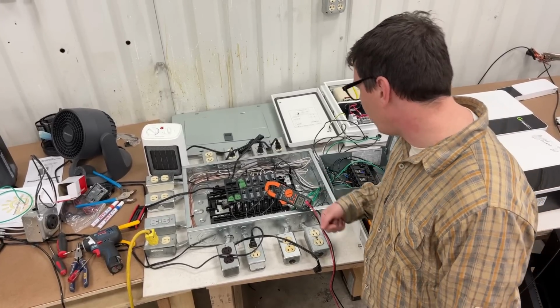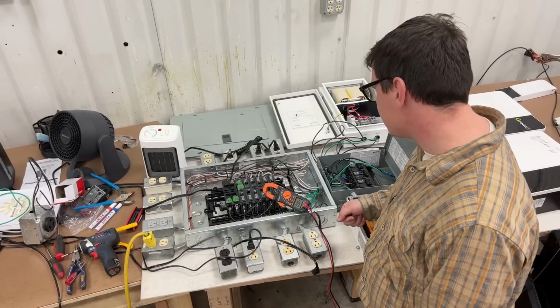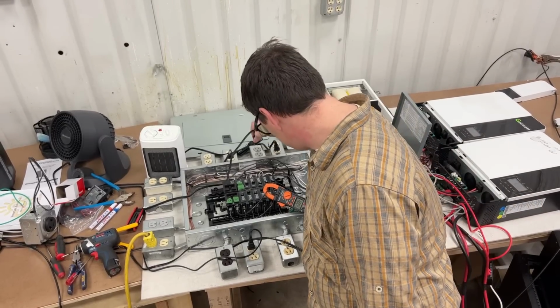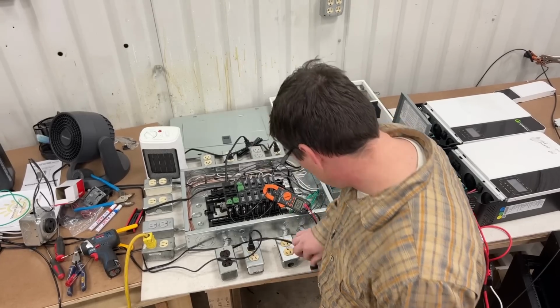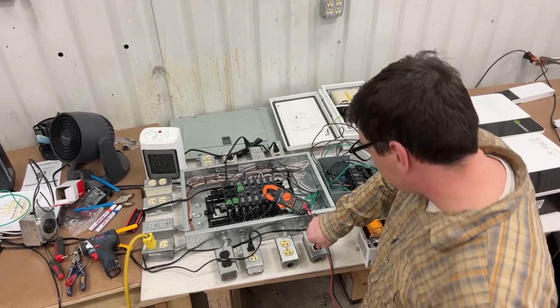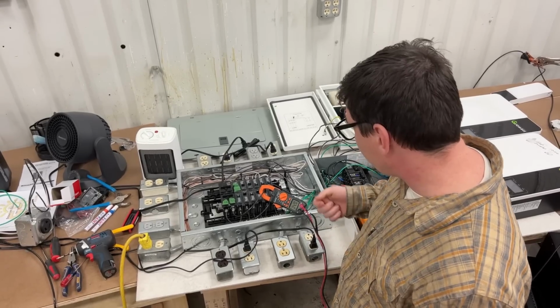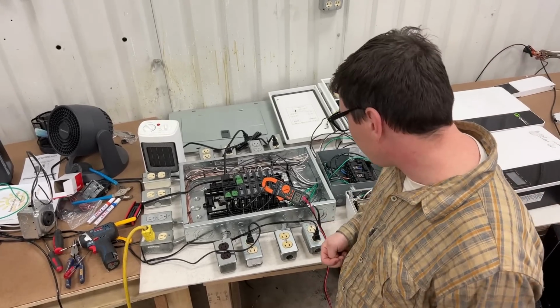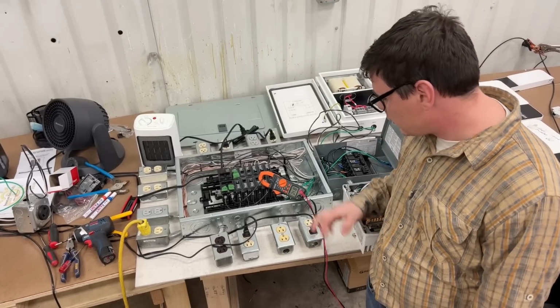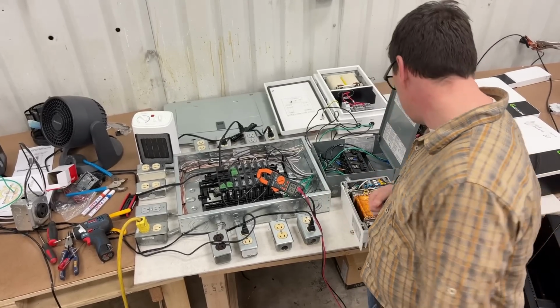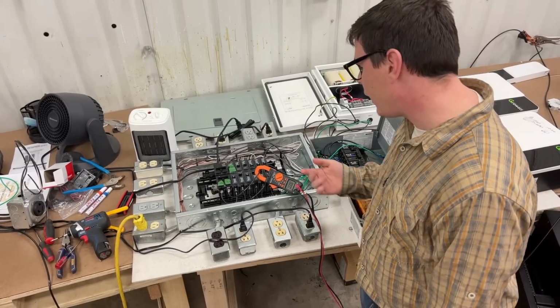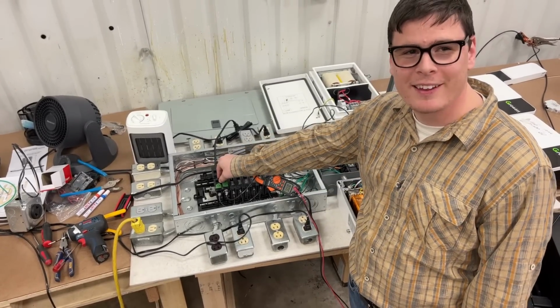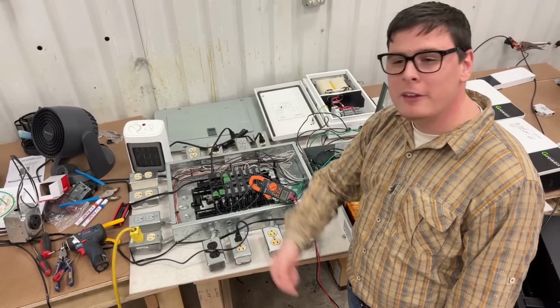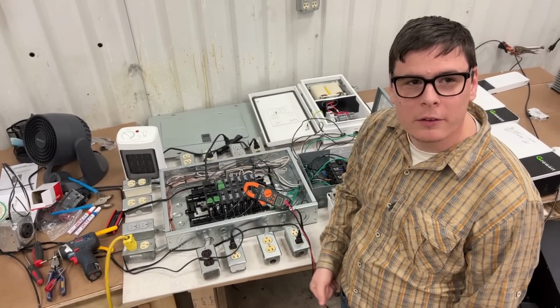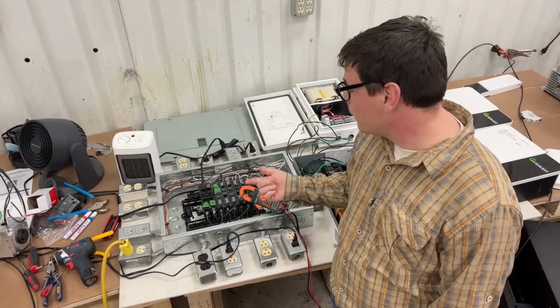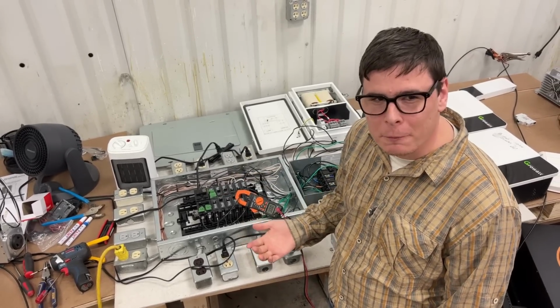What do I have on the other line I can pull off to sort of drive this thing? Let's see. I think, yeah, perfect. So this is total imbalance. I'm pulling 42 amps on the thing. Totally imbalanced. What's going to happen? As you can see, the transformers, there you go. Now, the cool thing is, when this tripped, it tripped the 120 volt hot lines, line 1 and line 2. So the neutral's still here, but the hot lines got tripped by overcurrent protection.